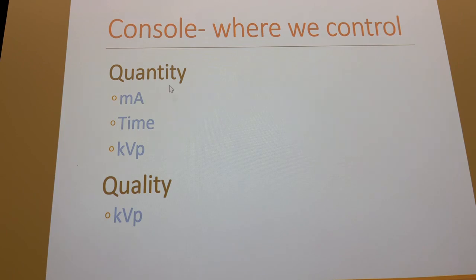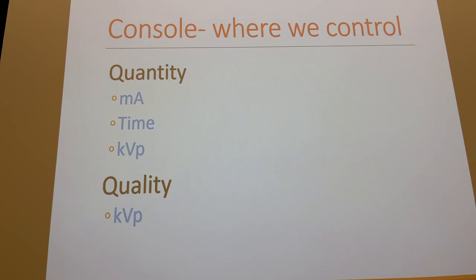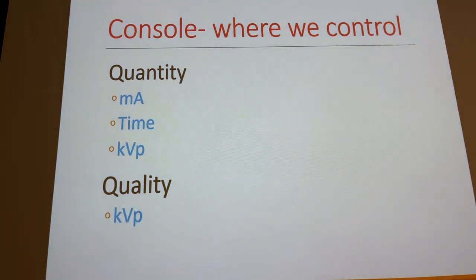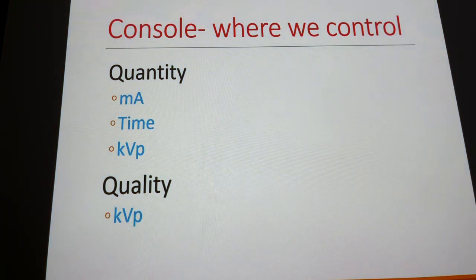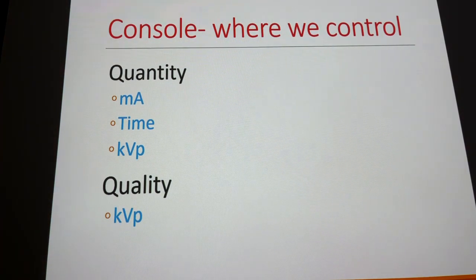For quantity, we use KVP, MA, and time. For quality, we use KVP — as we'll discuss as the semester goes on, there are other factors, but that's the main approach. From the control panel, we also control other things like focal spot size and photocell selectors.